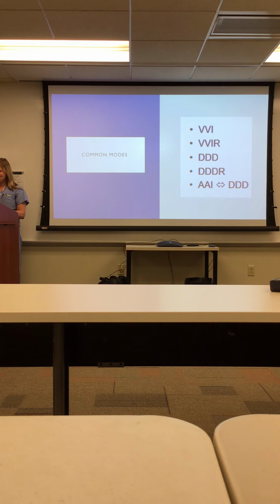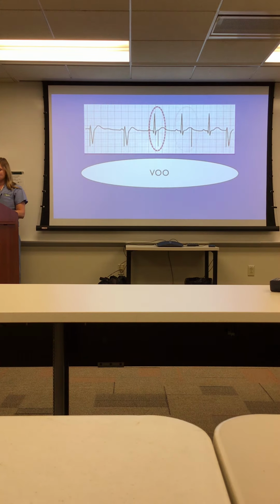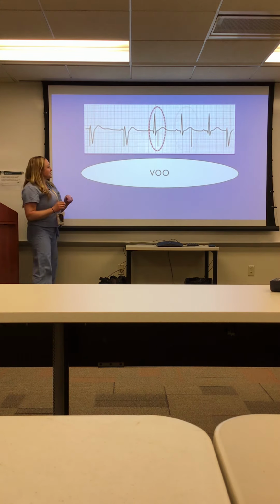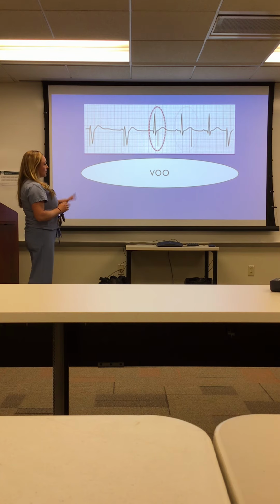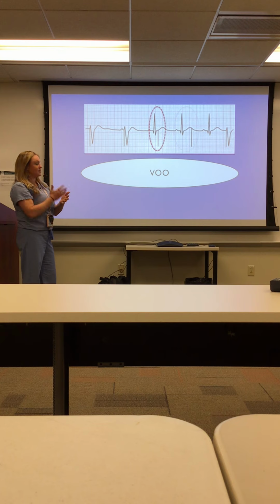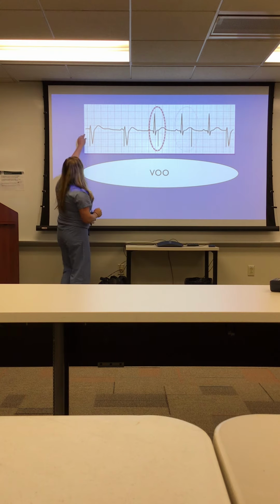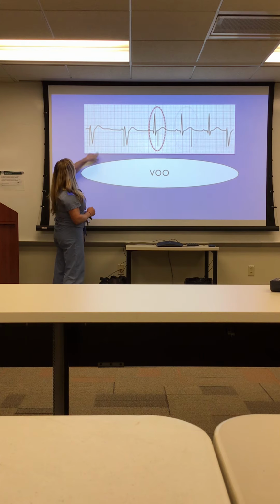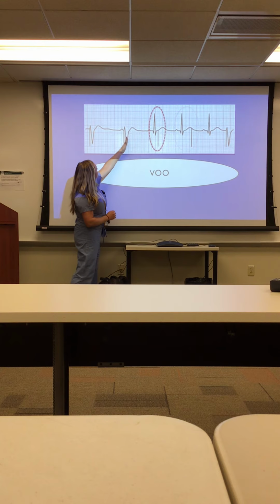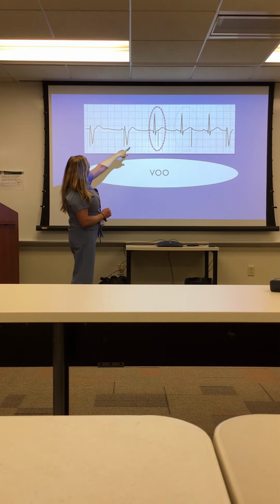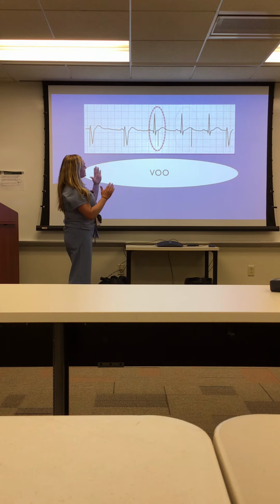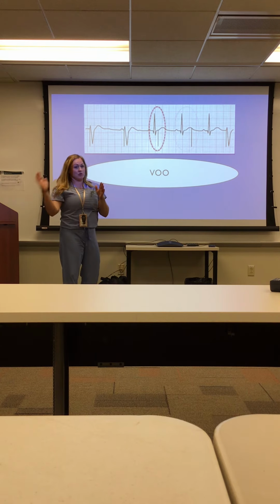Okay, so we already went over the common modes that they'll typically be programmed to. Now we'll go through and talk about each of these strips and what we expect to see. Like we said, the VOO mode is just going to deliver paced beats at a set rate, which we'll say is 60 beats a minute in this case. So you can see here, there's a paced beat lined up right before the ventricle, and then we see a wider QRS to follow. So that's a captured ventricular beat, as is this one. Then we go to this one, and we actually see that falling behind, but that just tells us that it's not sensing anything. It's just marching through at the programmed rate that it's set to.